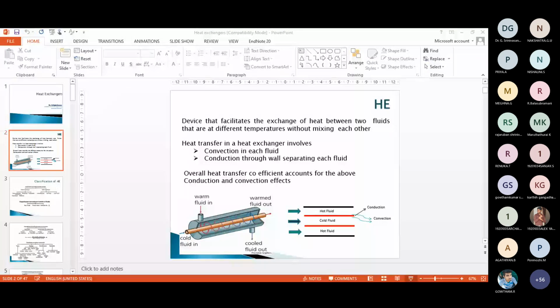So for gas to fluid, when the beta value is more than 700 square meters per cubic meter, it is called compact type. When it is less than 700, it is called non-compact. Whereas on the liquid side, when the beta value is more than 400 square meters per cubic meter, we can call it compact type. If it is less than 400 square meters per cubic meter, then it is non-compact. This is one way we can classify the heat exchangers.